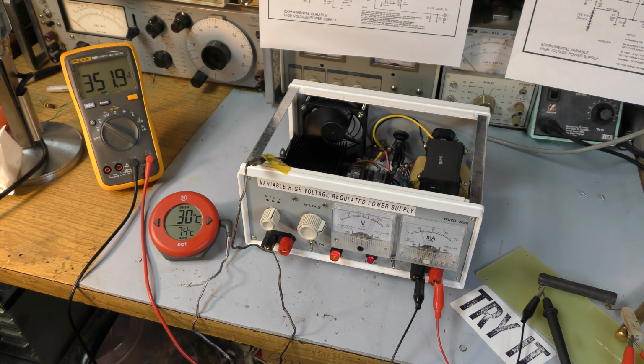Well, whatever the differential is, it's steady. Looks like it did stop it from climbing, because it was as high as 31, now it's back to 30. So the heatsink is certainly not getting any warmer. The fan is keeping up with it. Remember, this is an exhaust fan, pulling air away from the heatsink. Looks like we have stability.